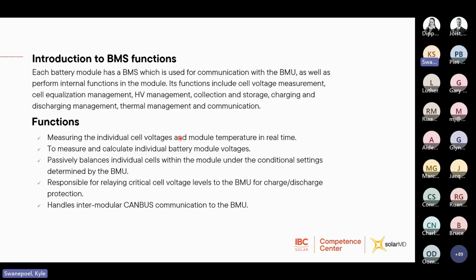Okay, cool. So we can just quickly get into what exactly we are looking at from a more technical spec on the BMS, the BMU, just to run through what the BMS does. So each battery module has a BMS, and this is primarily used to communicate its individual battery module information to the BMU. And it also performs internal functions, so cell voltage measurement, cell equalization. This is what you requested earlier. It was Dwayne that asked. Each battery module has the BMS, which performs passive balancing on that specific module.